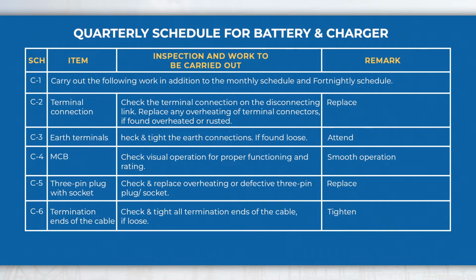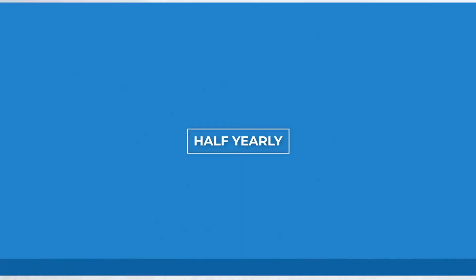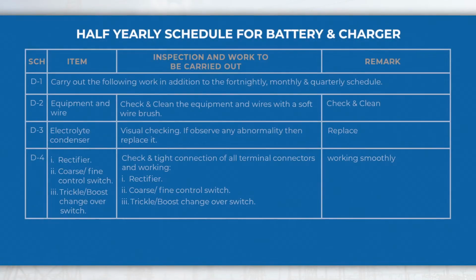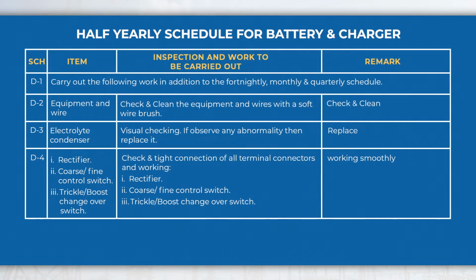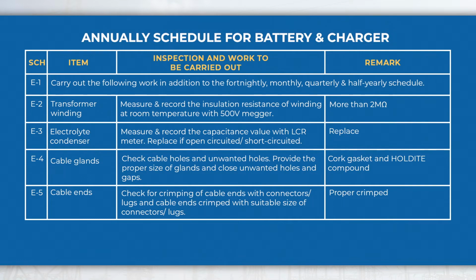Quarterly schedule: perform activities like checking the terminal connection on the disconnecting link and overheating or defective 3-pin plug socket, etc., in addition to fortnightly and monthly schedule activities. Half-yearly schedule: perform activities like checking the working of the rectifier, coarse fine control switch and trickle boost change-over switch, etc., in addition to fortnightly, monthly and quarterly schedule activities. Annual schedule: perform activities like measuring the insulation resistance of transformer winding and capacitance of electrolyte condenser, etc., in addition to fortnightly, monthly, quarterly and half-yearly schedule activities.